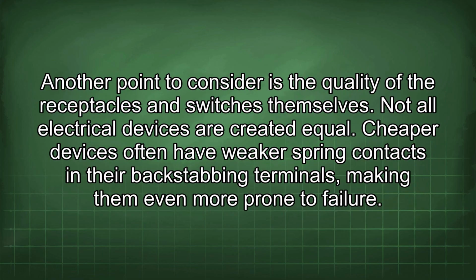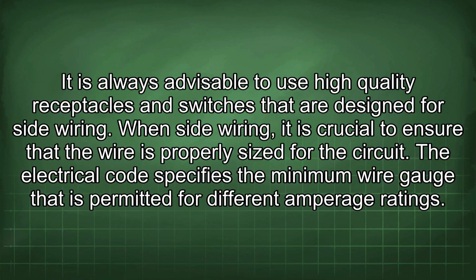Another point to consider is the quality of the receptacles and switches themselves. Not all electrical devices are created equal. Cheaper devices often have weaker spring contacts in their backstabbing terminals, making them even more prone to failure. It is always advisable to use high-quality receptacles and switches that are designed for side wiring.